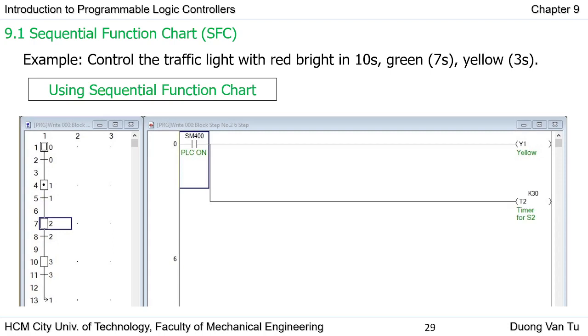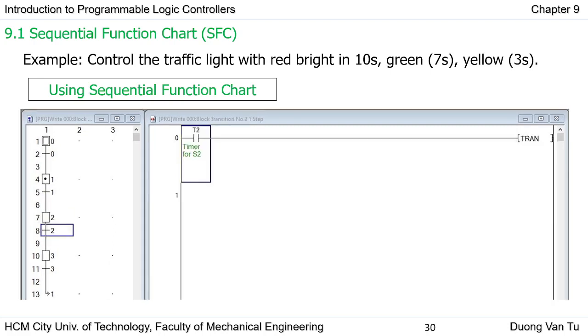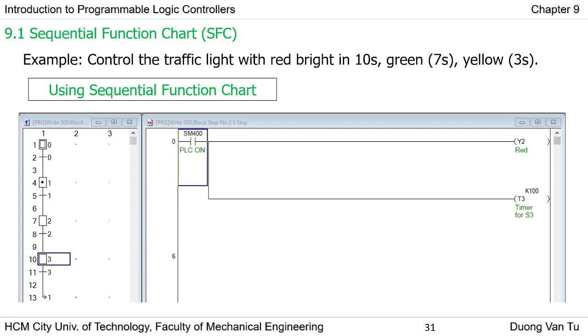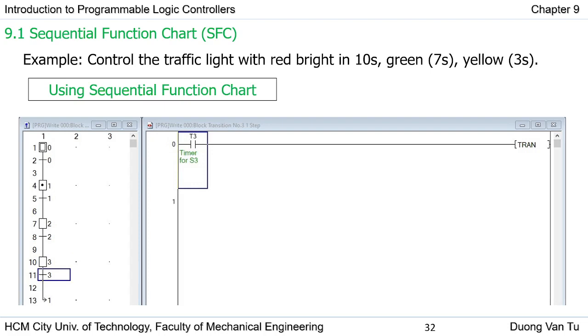For step two, it turns on the yellow light and starts counting timer two for 3 seconds. After timer two reaches its setting value, it switches to step three, where we turn on the red light and start counting timer three for 10 seconds. When timer three reaches its setting value, we return to step one using a jump instruction. In step one there is a point indicating that a jump instruction from another step goes to this step.